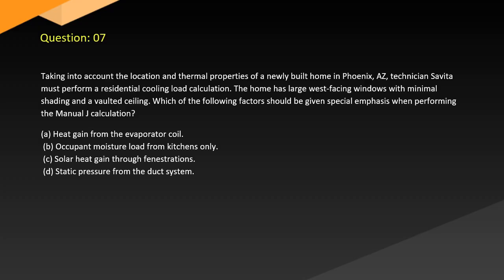Question 7. Taking into account the location and thermal properties of a newly built home in Phoenix, technician Savita must perform a residential cooling load calculation. The home has large west-facing windows with minimal shading and a vaulted ceiling. Which of the following factors should be given special emphasis when performing the Manual J calculation? A. Heat gain from the evaporator coil. B. Occupant moisture load from kitchens only. C. Solar heat gain through fenestrations. D. Static pressure from the duct system.